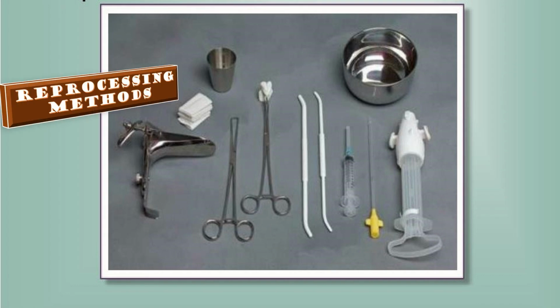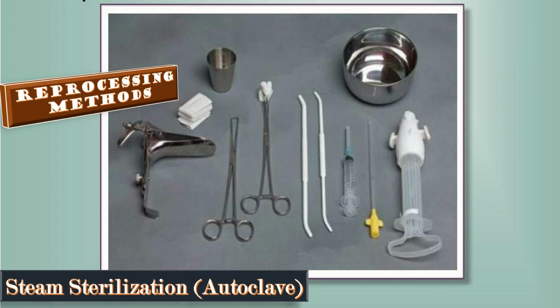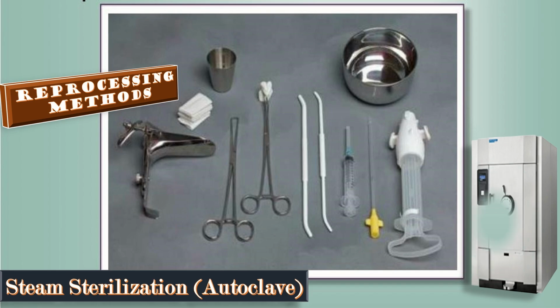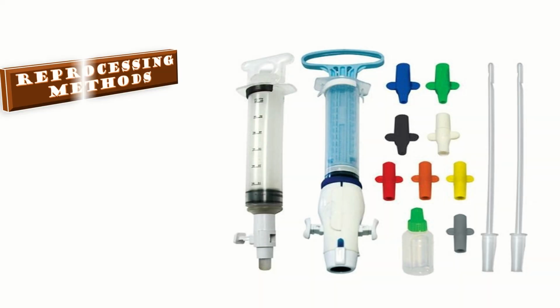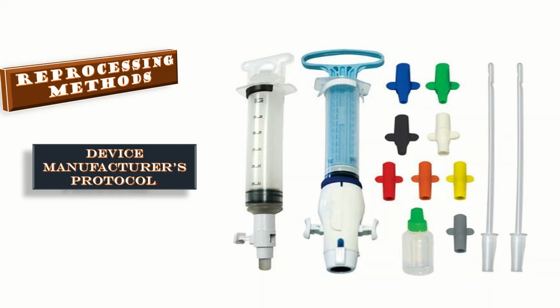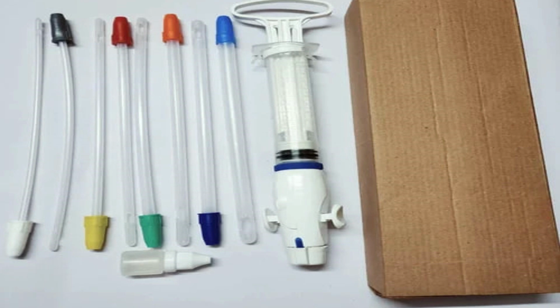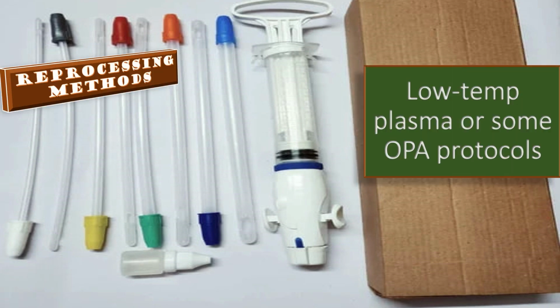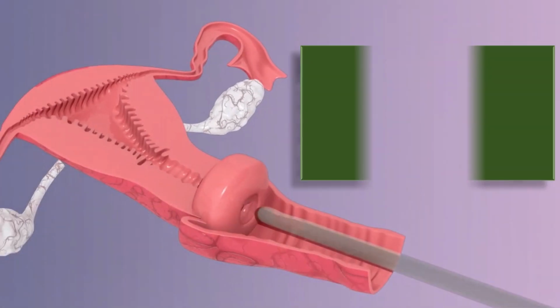In the reprocessing methods, the preferred method was steam sterilization or autoclave for heat stable parts when the IFU allows. High level disinfection or sterilization must be validated against the device manufacturer protocol. Some HLD and sterilization methods, for example low temperature or some OPA protocols, were not recommended by validated study for specific devices.